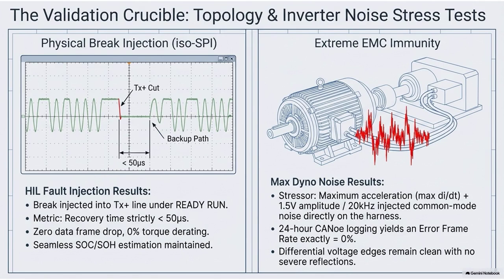The strict 59 to 61 ohm window is a binary, mathematically perfect proof of the physical integrity of the entire network. It's like a pass-fail grade for the physical wiring. Exactly. If it passes that single test, the engineers know the physical structure is fundamentally sound.